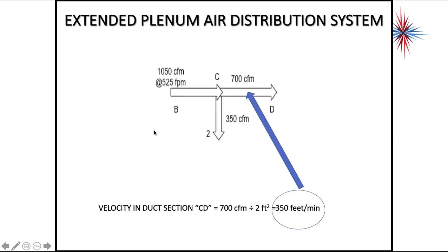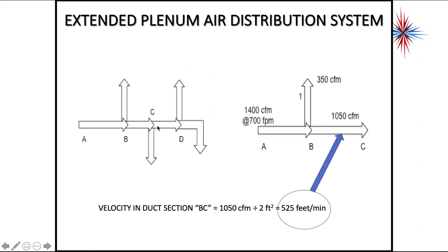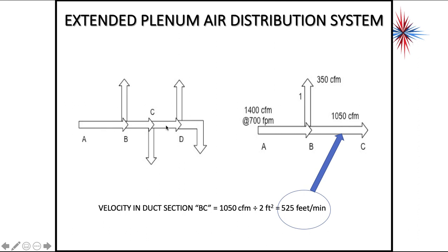Then we go to my next one, which is after point C to D, so if we look at my whole run here, we're talking this area right there, between C and D. I have my 1,050, I'm losing 350, so what I have remaining is 700 CFM. Divide that by my 2 square feet, my velocity here, between C and D, is 350 feet per minute.